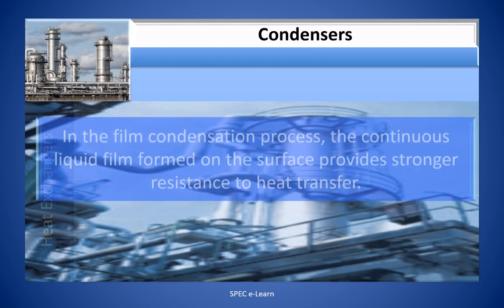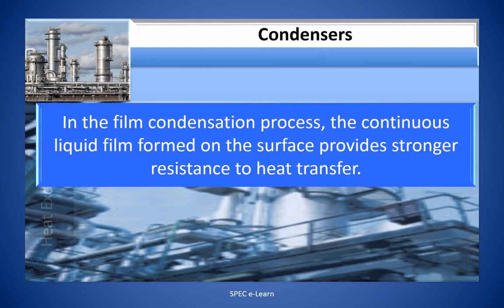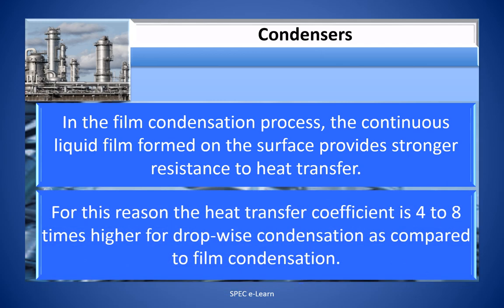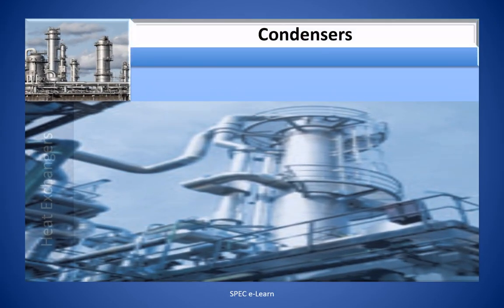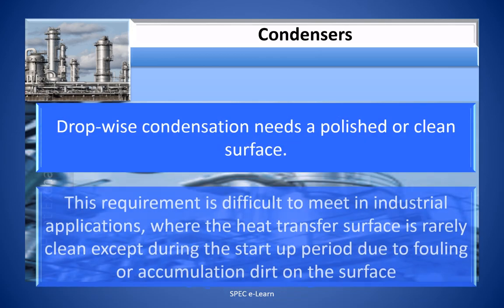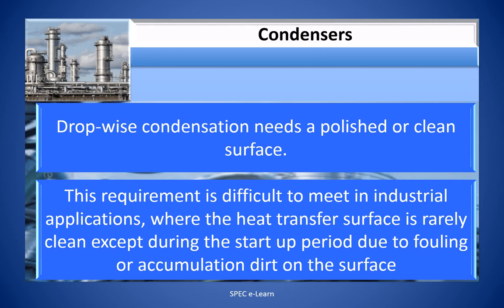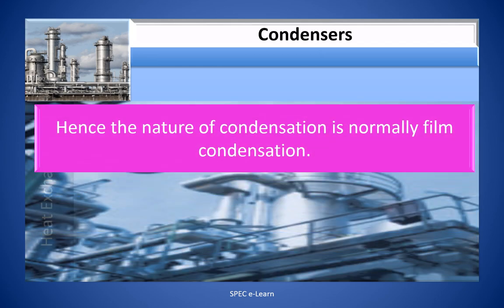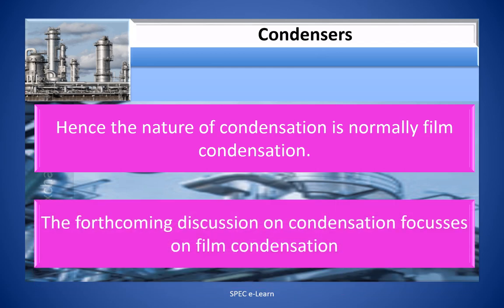In film condensation, the continuous liquid film formed on the surface provides stronger resistance to heat transfer. For this reason, the heat transfer coefficient is 4 to 8 times higher for drop-wise condensation compared to film condensation. However, drop-wise condensation requires a polished or clean surface — a requirement difficult to meet in industrial applications where the heat transfer surface is rarely clean due to fouling. Hence, the nature of condensation in practice is normally film condensation, and the forthcoming discussion focuses on film condensation.